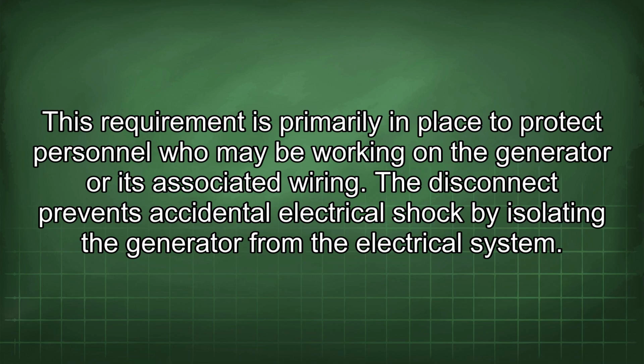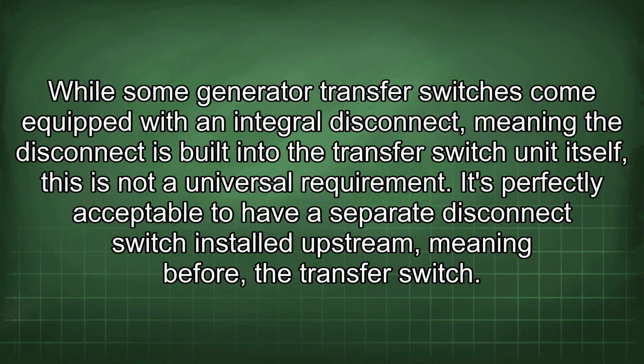The disconnect prevents accidental electrical shock by isolating the generator from the electrical system. While some generator transfer switches come equipped with an integral disconnect, meaning the disconnect is built into the transfer switch unit itself, this is not a universal requirement. It's perfectly acceptable to have a separate disconnect switch installed upstream, meaning before the transfer switch.